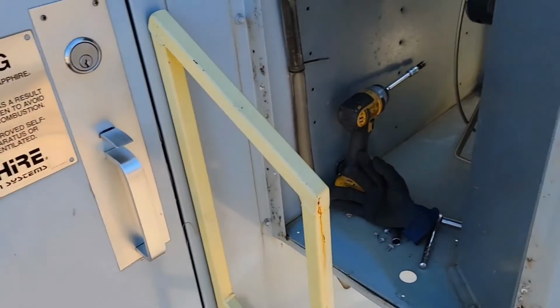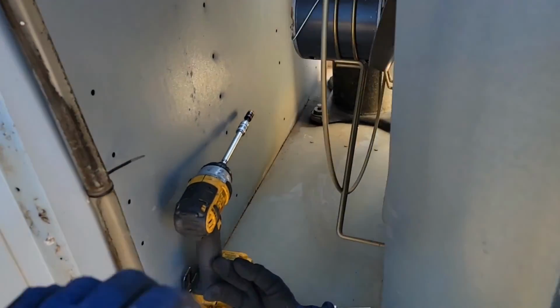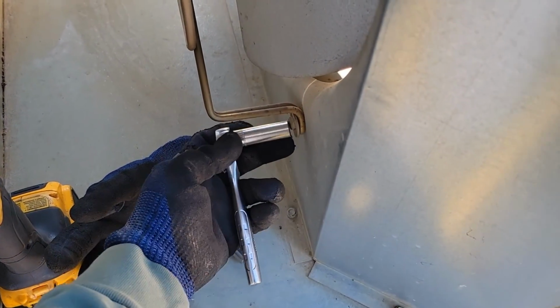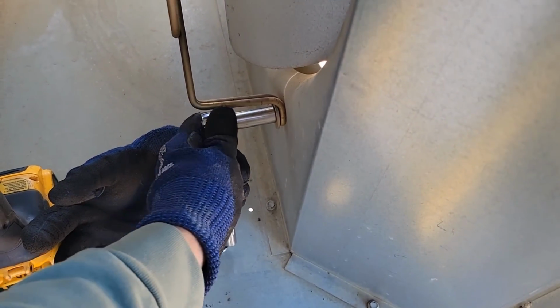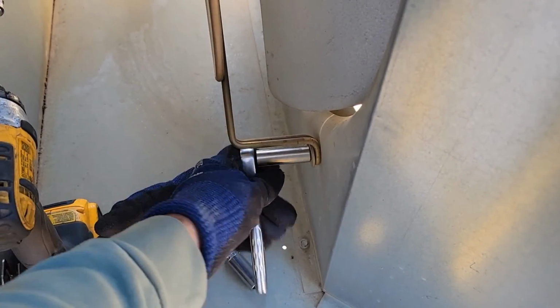Okay. Close this door so you guys can actually hear because it's so loud in there. I'm gonna take out the 4 bolts that are holding the bracket that holds this outdoor fan so I can actually check the bearings because it's hard to get my hand in there. And it's a 7/16 socket, just in case you were curious. I'm gonna take these 4 bolts out and I'll take the wiring loose, get this fan out of here.